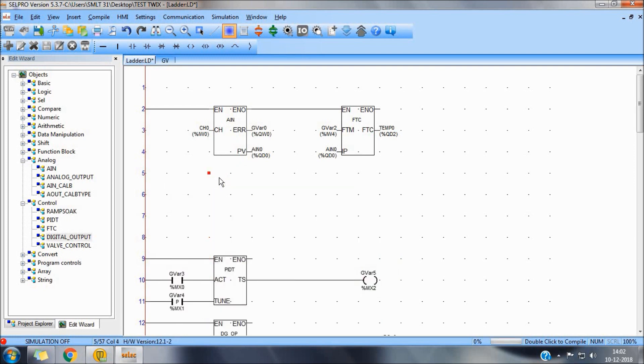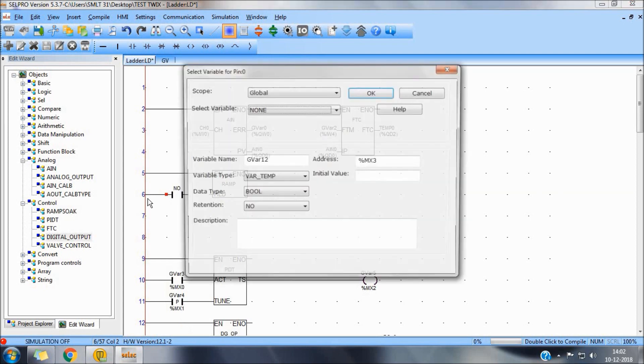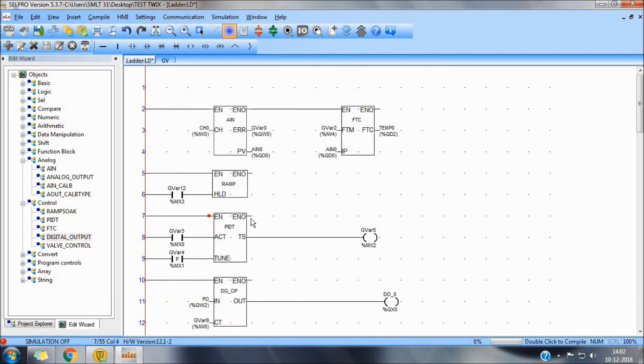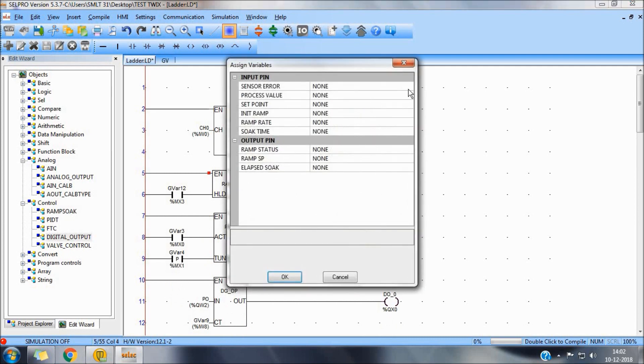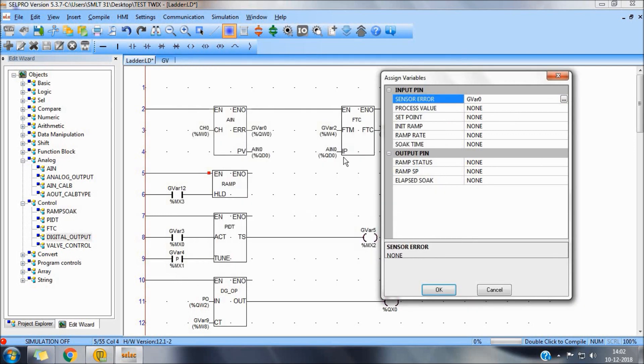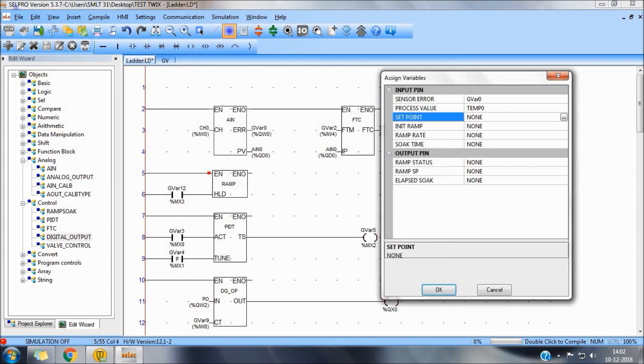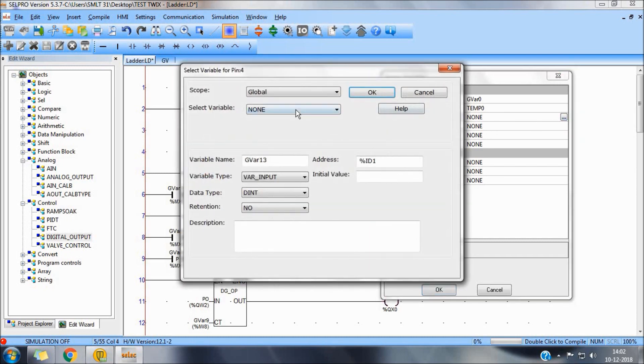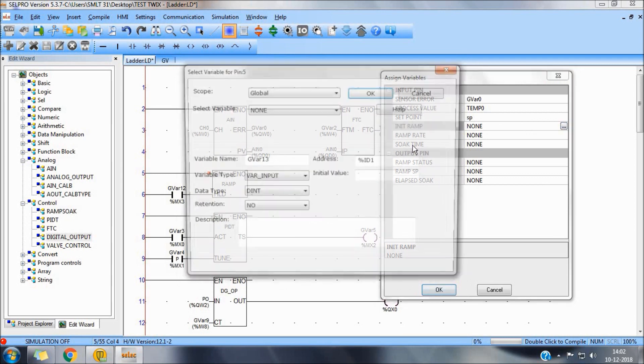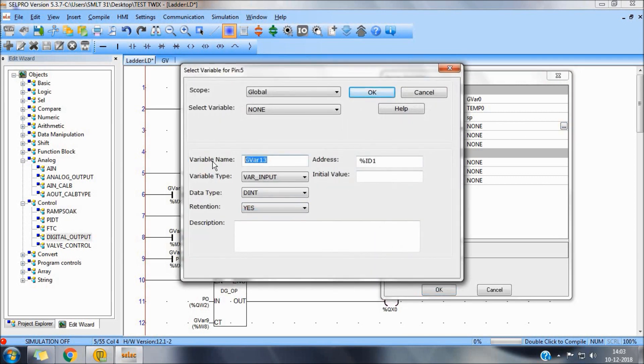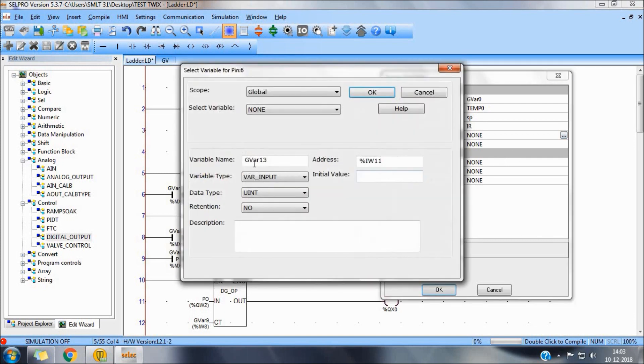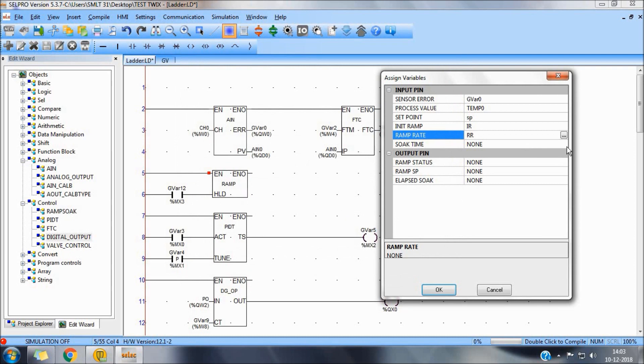We can use the same function for RAMPSOAK hold pin to stop function of RAMPSOAK if needed. Again, the same sensor value. TEMP0. Set point. Initial Ramp. Say for example, 27 degrees. Ramp rate. As 60 degrees per hour.